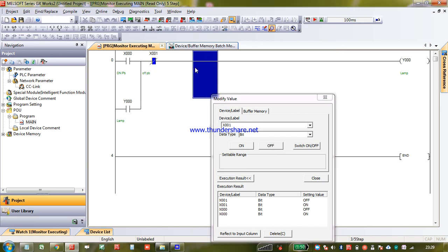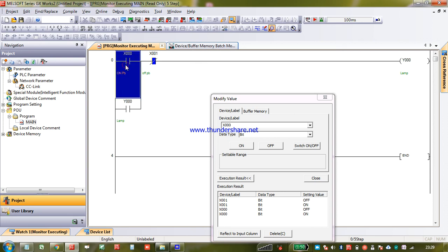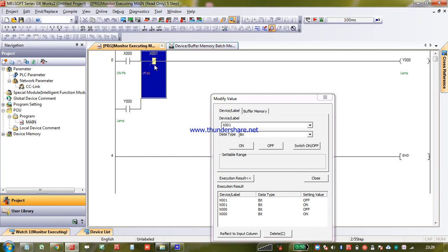If I release it, it will become normally closed. We should not get confused with NO contact and NC contact. Normally the NO contact will close if the input turns on, and the NC contact will remain closed until the input turns on. These two we normally get confused. In some situations, the stop or off buttons will be wired to an NC element.